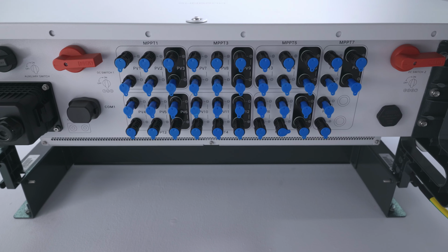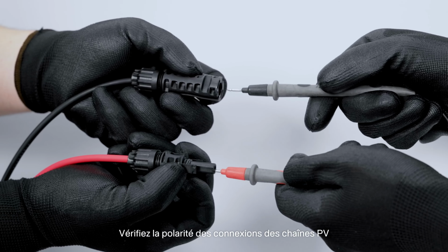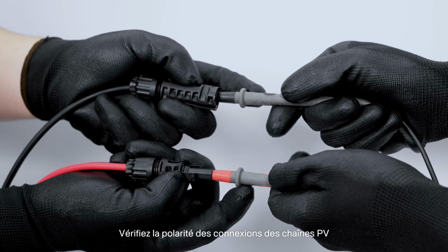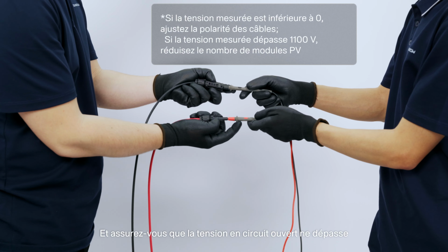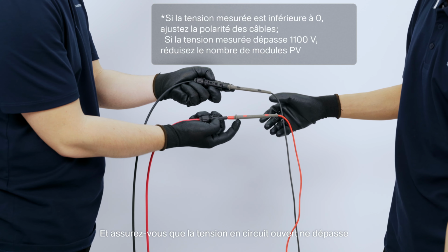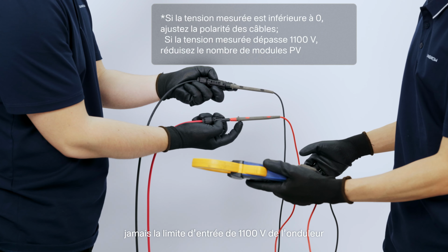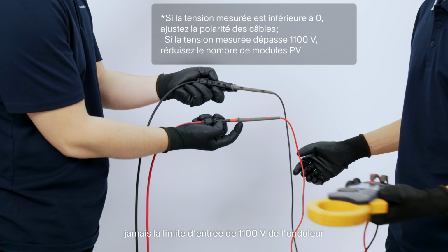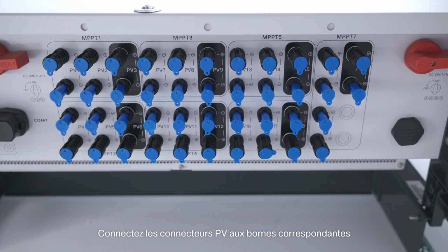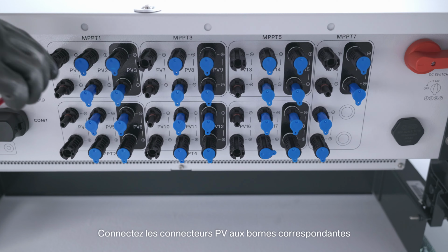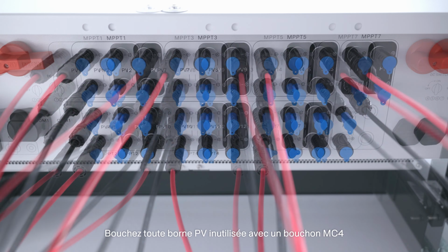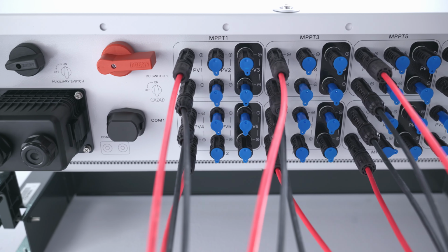Rotate the DC switch to off position. Check the cable connection of the PV string for polarity correctness, and ensure that the open circuit voltage in any case does not exceed the inverter input limit of 1100 volts. Connect the PV connectors to corresponding terminals. Seal any unused PV terminal with a terminal cap.